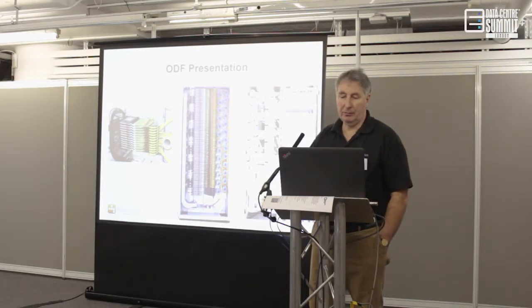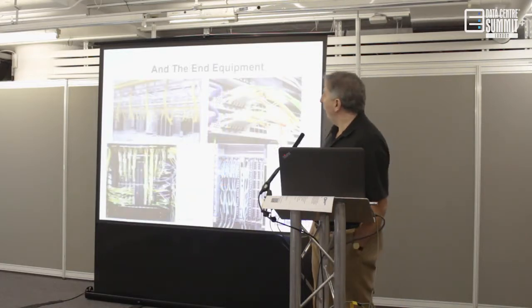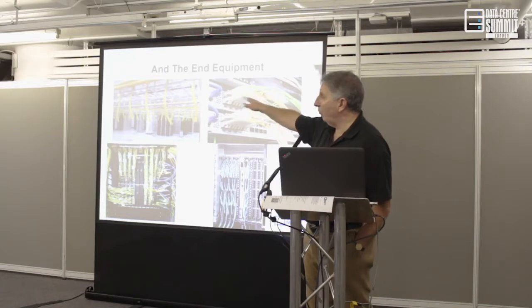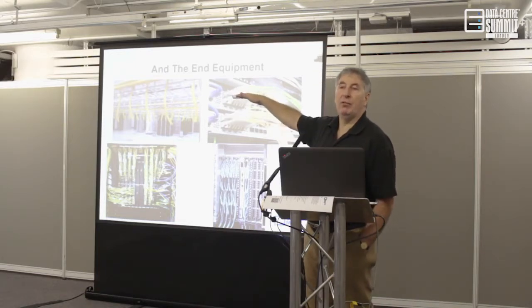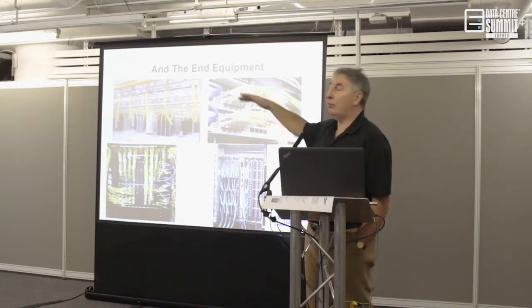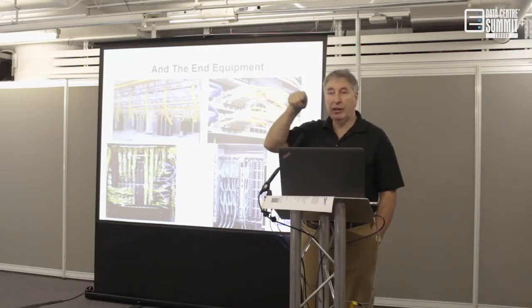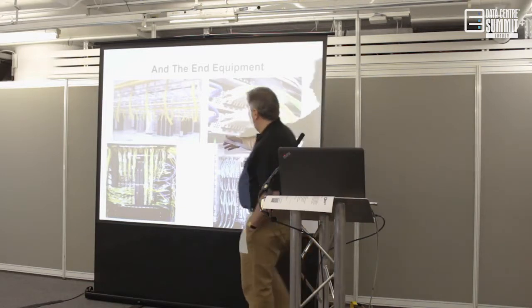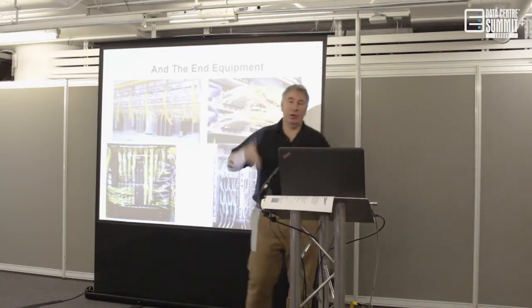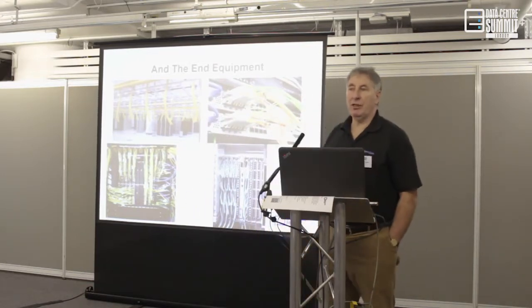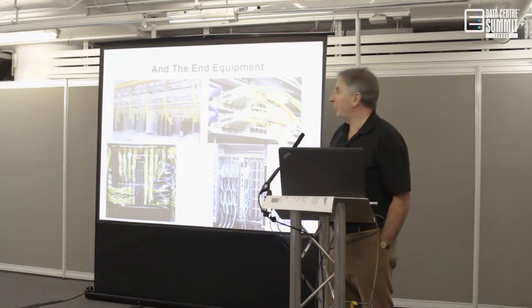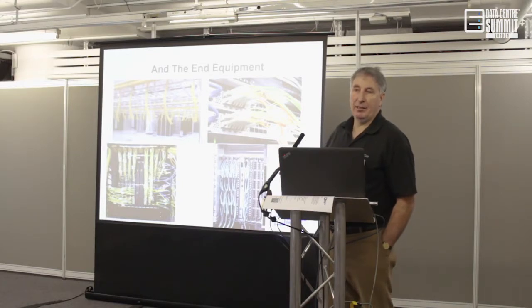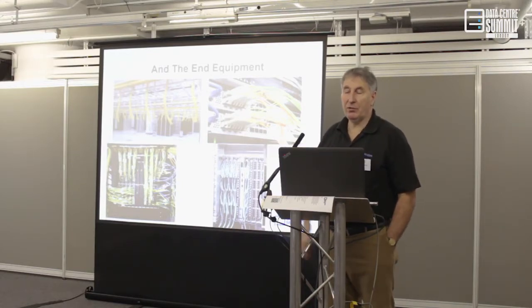It needs that connectivity. And of course, what we may end up doing is we may end up putting a whole tray infrastructure above the actual racks before they even go in, so that you can lay all the cables, so you can leave it right to the last minute, and then lay the cable on the top, and then you can see you've got tubes then to put your fibres down to protect them. Because there is some delicacy to the fibres. And then the end equipment, of course, you've got a whole load of fibre to get to them. And so there's many different methods and techniques.